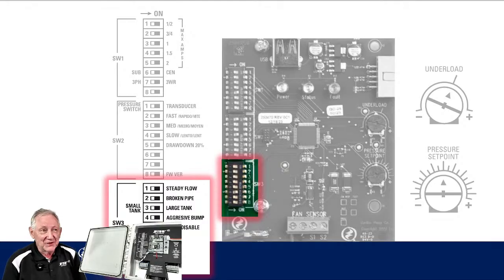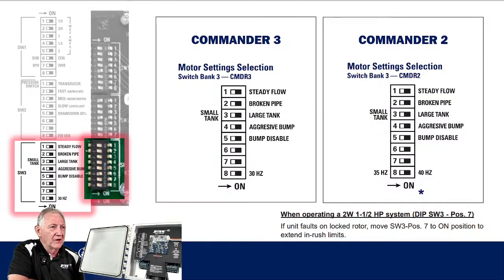Again, folks, first bank tells you what kind of pump motor you're running. Second bank, what kind of a switcher you're going to use to operate it, transducer or a pressure sensor switch. That third bank, as I mentioned early on, is kind of a little bit of a catch-all down there. Let me see if I've got a better view of that bottom bank there. There we go. So when we look at the bottom bank, and again, when you look at the difference between the Commander 2 inlay versus the Commander 3, there are subtle differences, slight differences, but they're pretty important. But you can see those differences on the screen now.